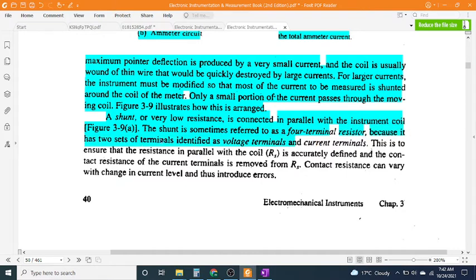It has two sets of terminals identified as voltage terminals and current terminals. This is to ensure that the resistance in parallel with the coil is accurately defined and the contact resistance of the current terminals is removed. Contact resistance can vary with change in current level and thus introduce errors.